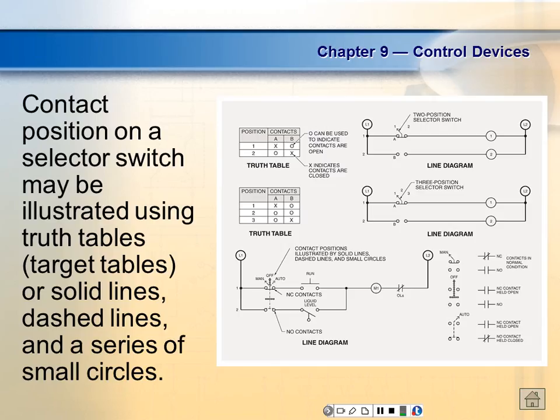The manufacturer just sells a 3-position selector switch - what can you use it for? Well, anything you need a 3-position selector switch for. One application might be to turn the sump pump on, and that's what you'd label once you put it in your application. The manufacturer has no idea, so they give you these truth tables to show what happens depending on what position you put the switch in. Does that make sense?